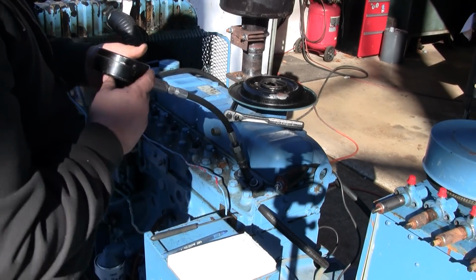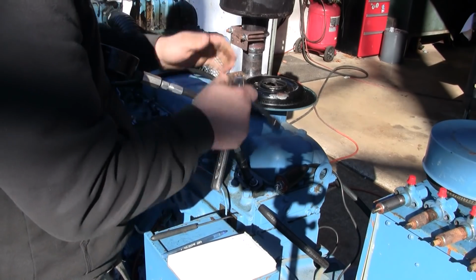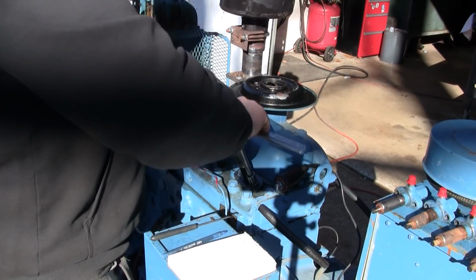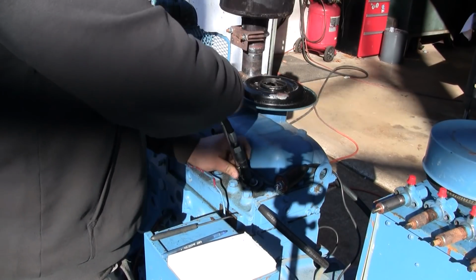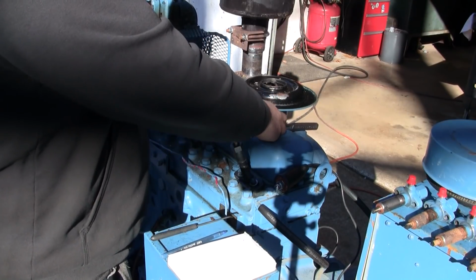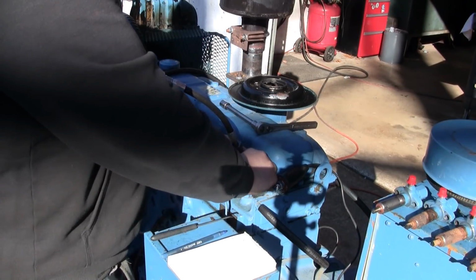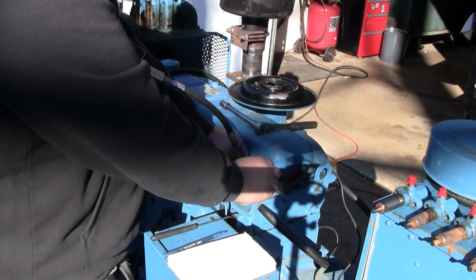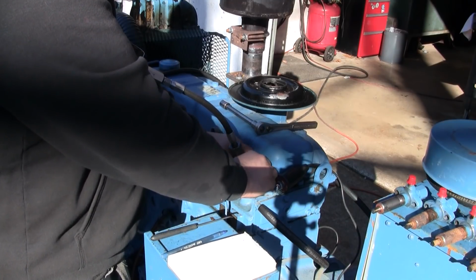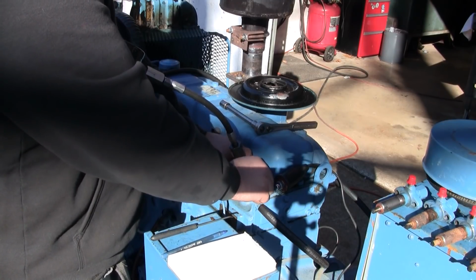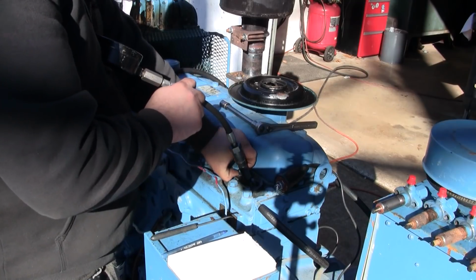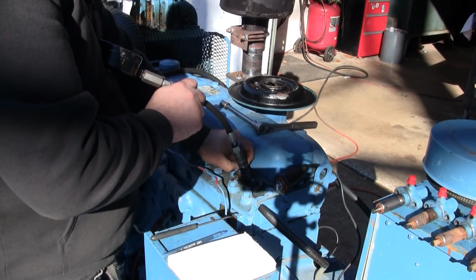Let's go back and try number 4 again, to make sure we get that same reading. If we don't get that same reading, well, we know something was either sitting under a valve, or maybe the gauge wasn't sealing correctly.